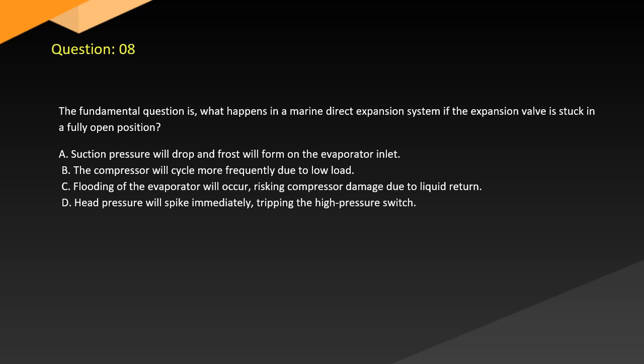Question 8. The fundamental question is what happens in a marine direct expansion system if the expansion valve is stuck in a fully open position. A. Suction pressure will drop and frost will form on the evaporator inlet. B. The compressor will cycle more frequently due to low load. C. Flooding of the evaporator will occur, risking compressor damage due to liquid return. D. Head pressure will spike immediately, tripping the high pressure switch.